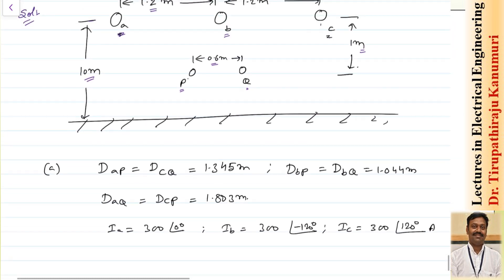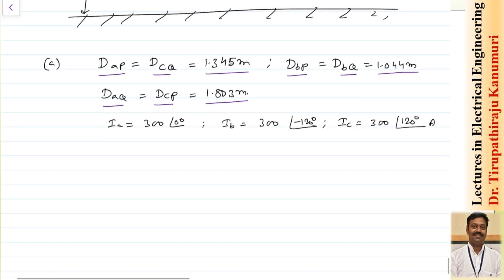Based on this configuration, I can calculate the distances. The distance D_AP equals D_CQ by symmetry — using the triangle method this gives 1.345 meters. Similarly, D_BP and D_BQ — both P and Q are symmetric with respect to B — gives 1.044 meters. D_AQ equals D_CP equals 1.803 meters. The current is balanced: I_A = 300∠0°, I_B = 300∠-120°, I_C = 300∠+120°.